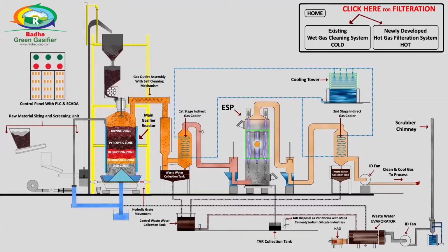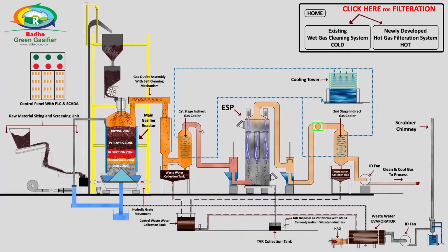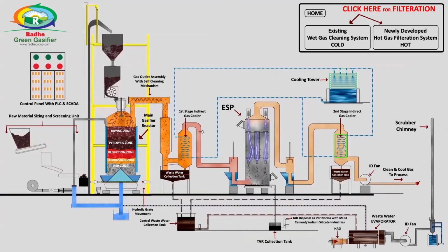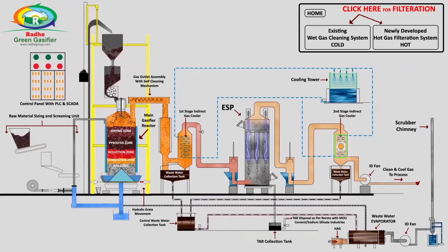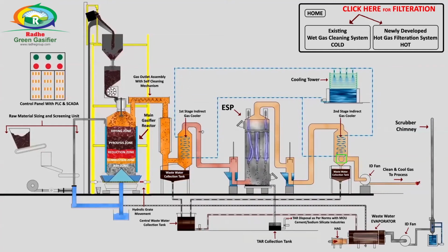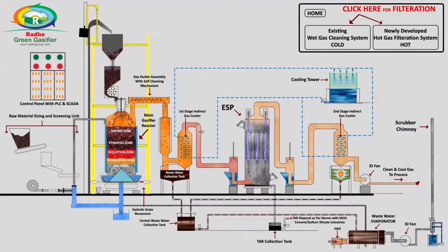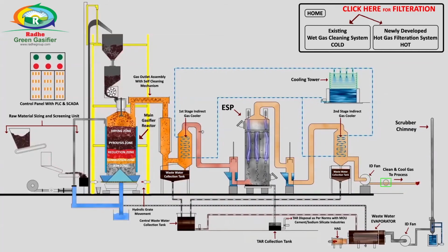Volatile particles get fully captured during the movement of electrons from negative to positive field and are collected into a discharge tube. Accumulated particles are discharged in the form of thick black liquid known as tar. Clean gas discharges from the ESP and enters the second stage of the indirect cooler, and the gas cools down to ambient temperature, and the available minor percent of moisture gets condensed and collected into the bottom tank in the form of wastewater. Practically clean and cool gas passes through the ID fan and toward the process.